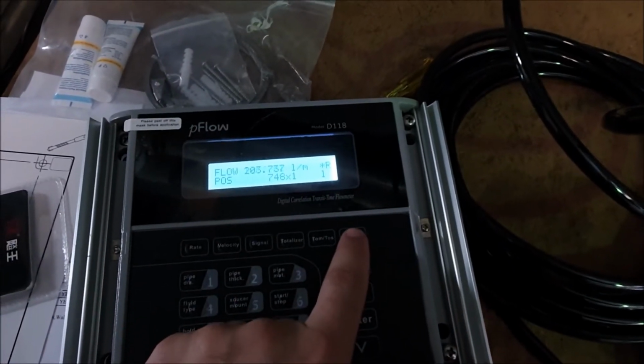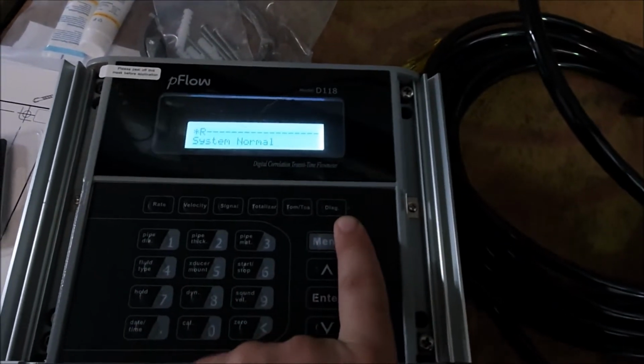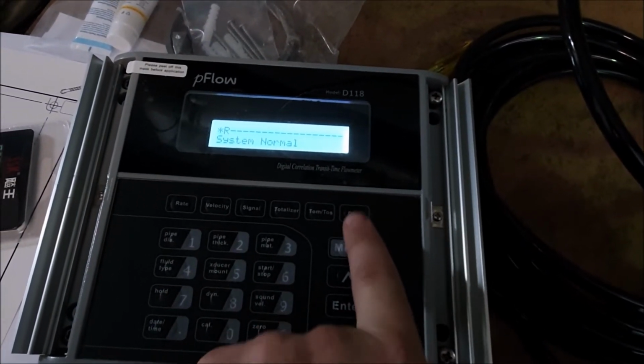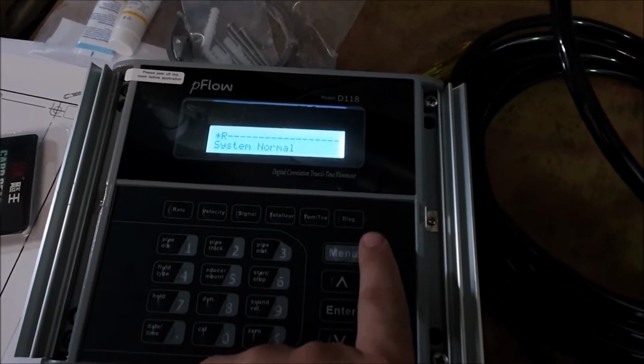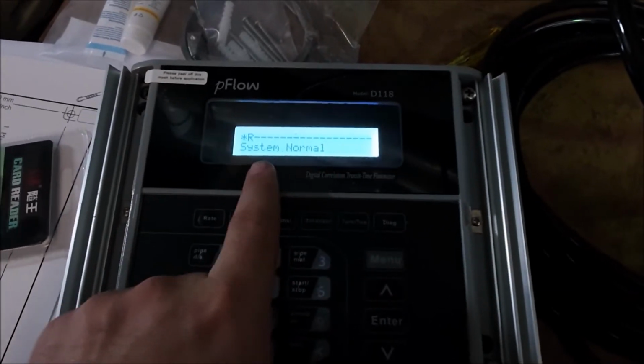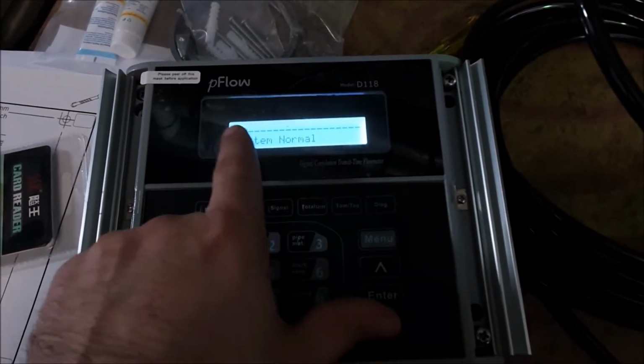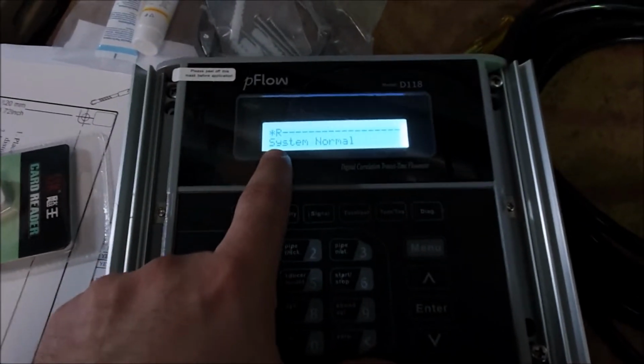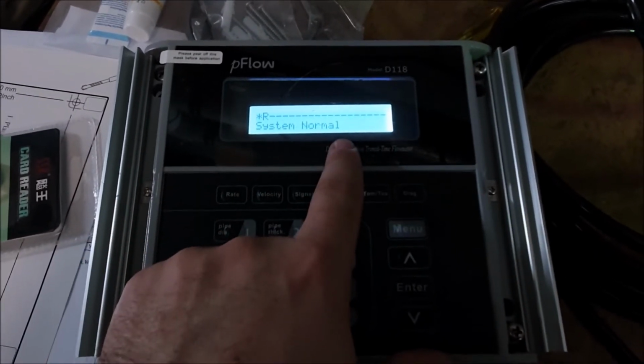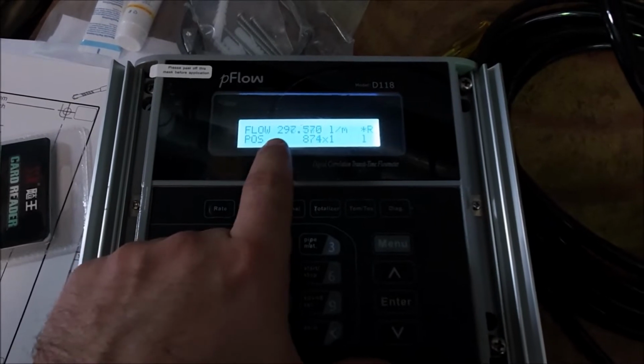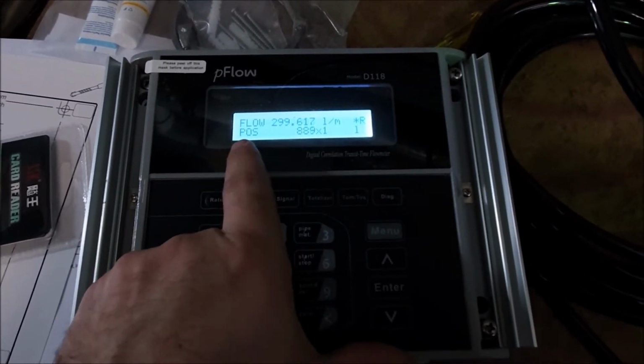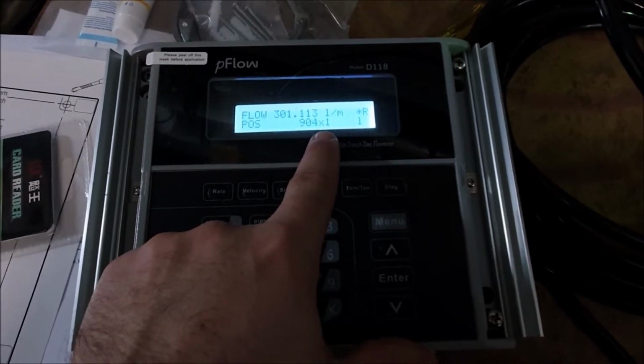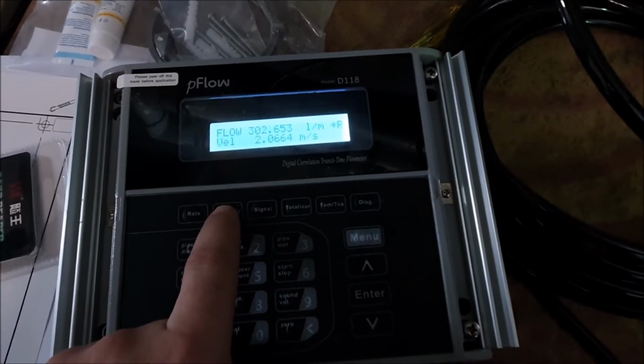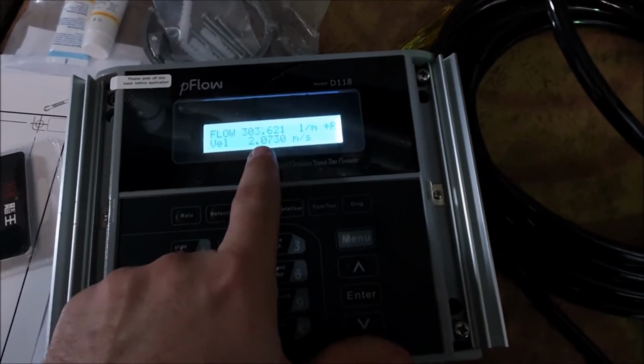And then maybe it might be of interest to go into diagnosis. If you have some issues and it's maybe not picking up your flow, you can use the diag button, and this will give some information if there's any problems. You can reference the manual then as to what these indications mean, but in this case we've just got system normal, everything looks good. Now if I go back onto flow rate, you'll see here's my current flow rate, and then below that is my totalized flow. You can look at velocity. You'll see here I've got 2.07 meters per second.